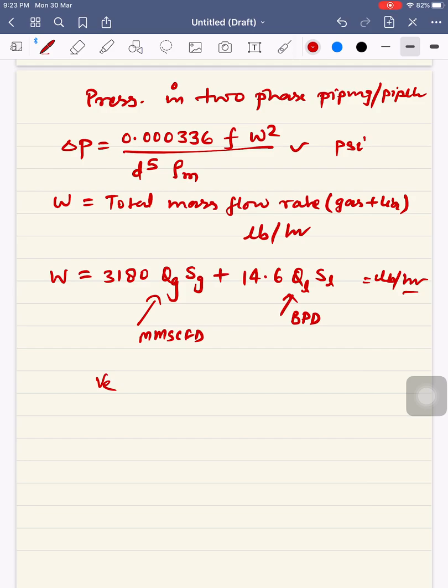For two-phase line you have erosion velocity calculation, minimum required diameter from Amin, and pressure drop from the formula. Based on your required flow rate or total mass flow rate, check whether ΔP is within allowable range. If it's beyond the allowable range, the diameter value should be increased. That's how we do two-phase line sizing.